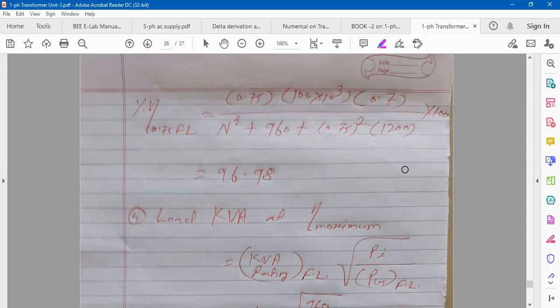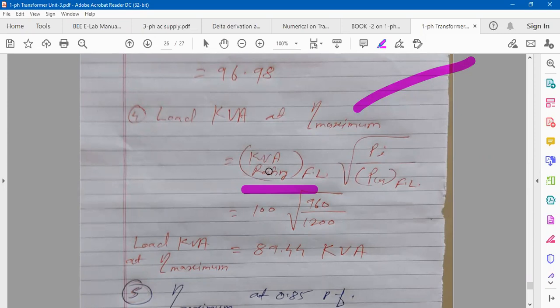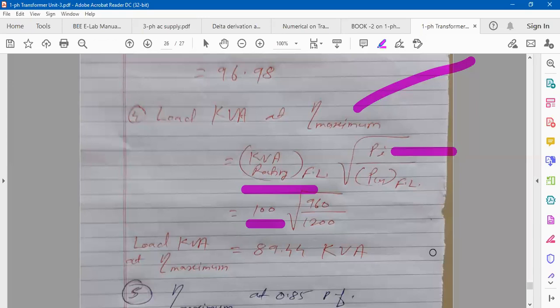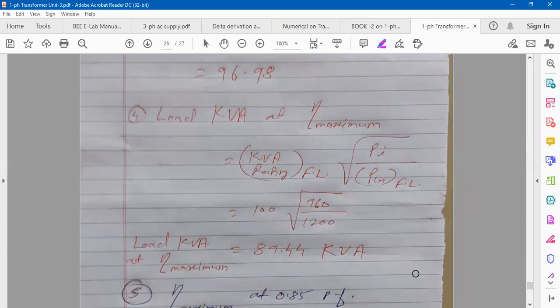Load KVA at maximum efficiency: directly use the formula — full load KVA rating × √(iron loss / full load copper loss). We want the answer in KVA, so put 100 directly. Iron loss = 960 W, full load copper loss = 1200 W. Load KVA at maximum efficiency = 89.44 KVA.